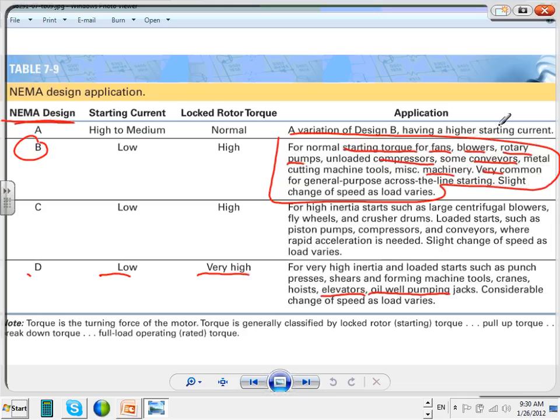So look at the very high locked rotor here. They use it for high inertia, things that you need to pull that are so heavy. Like if you put all of you guys in an elevator and I need to lift you. If you put a design B in it, that guy might say, okay, can somebody help me lift this? So design B, you might have 2 people helping it start, but when it starts, it just runs to get you the lift. So they use it on heavy inertia. Does it make sense? Like elevators?